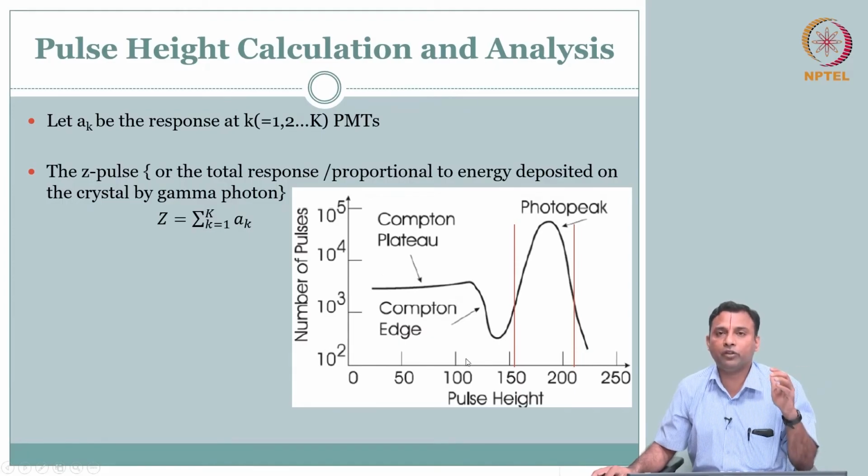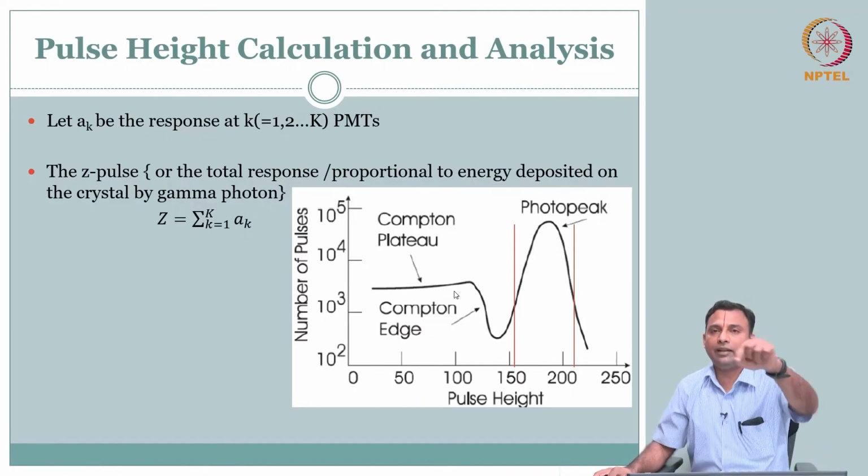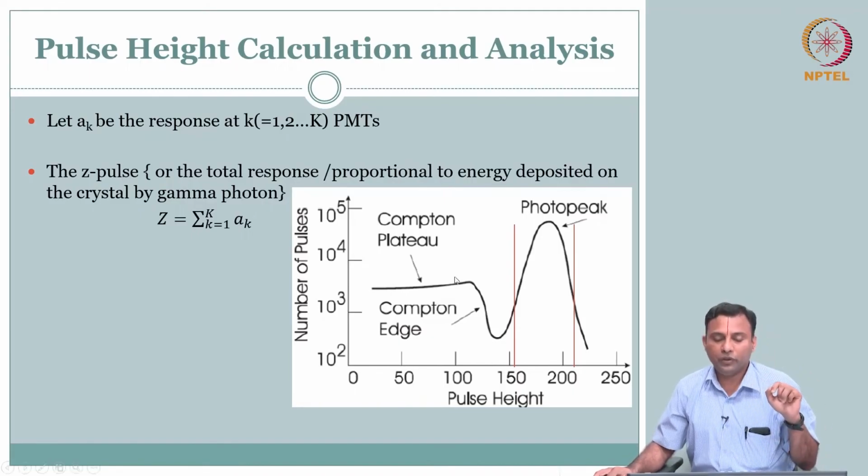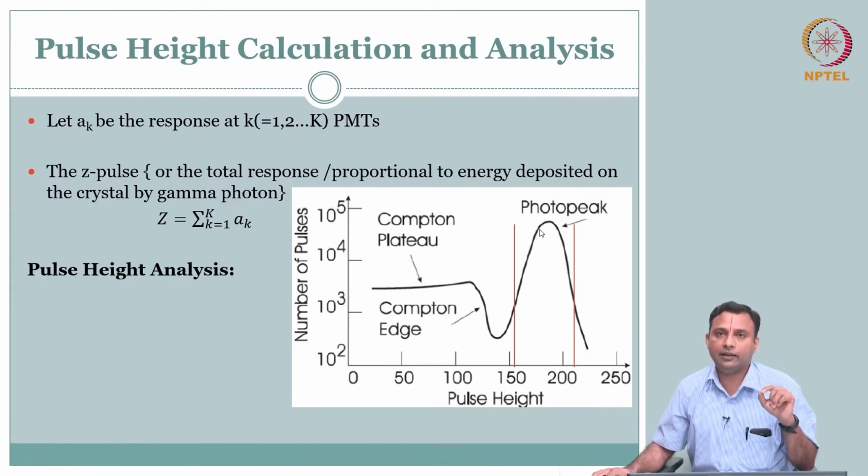You don't want to waste your effort to say where that signal came from, because you cannot say it, you know it's a Compton scattered signal. So you will be wrong to put that in the line of sight. So you collect all the signal, do this Z analysis, what we call pulse height analysis, and then we figure out which scintillation is produced because of the gamma, not the Compton scattered one, and which is not.